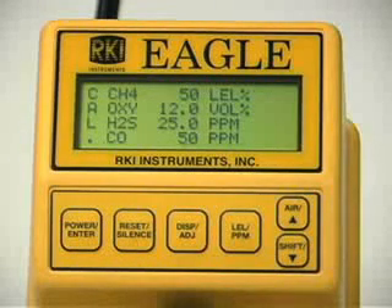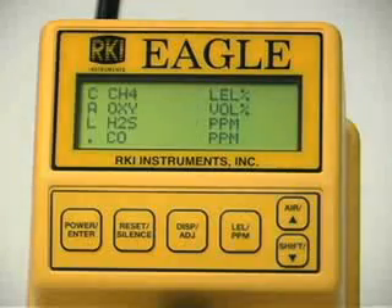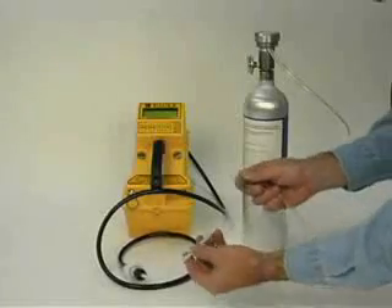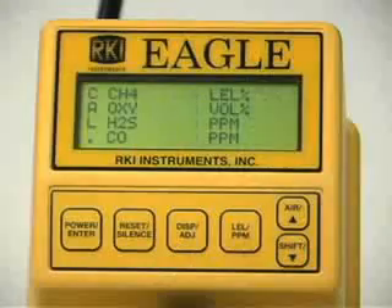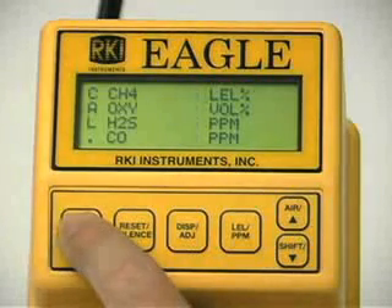The gas concentrations displayed in the calibration values screen must match the gas concentrations listed on the calibration cylinder. If all concentrations match, press the enter button. The gas readings will begin flashing. Now connect the tubing from the regulator to the Eagle's probe and wait approximately one minute or until the readings stabilize. Once the readings have stabilized, press the enter button to set the calibration to the program values. If your calibration was successful, the message auto calibration end displays followed by the calibration menu.